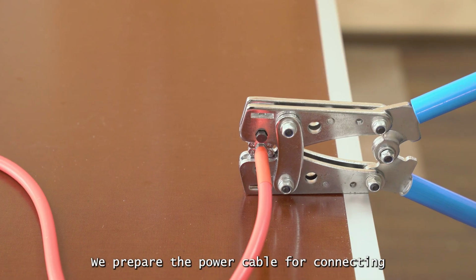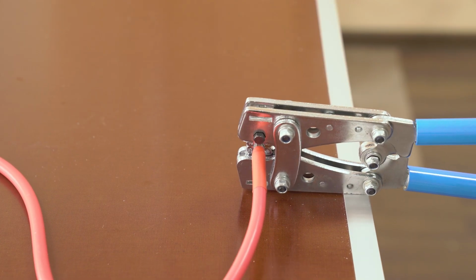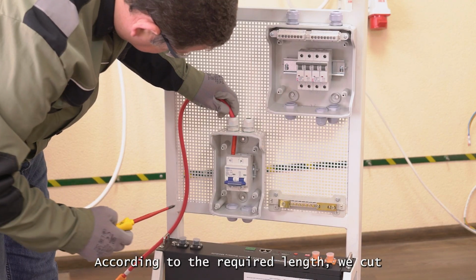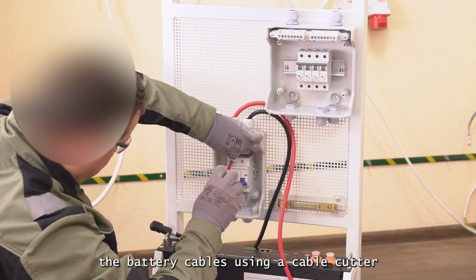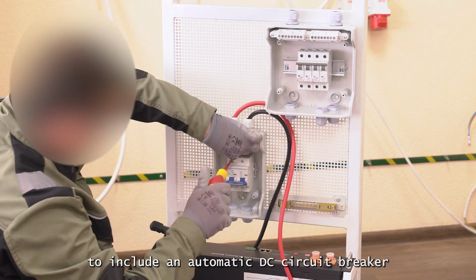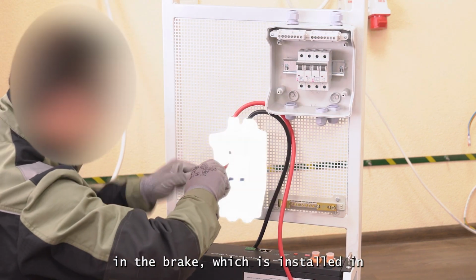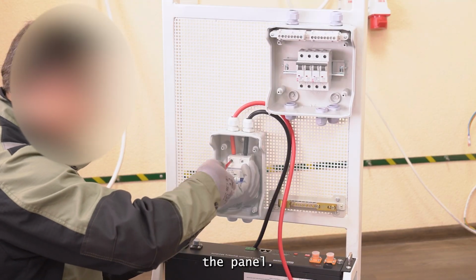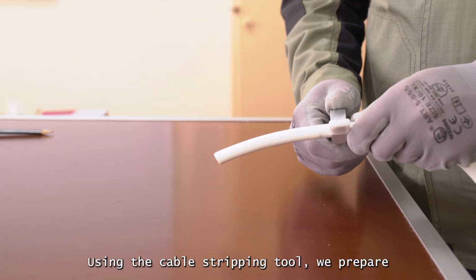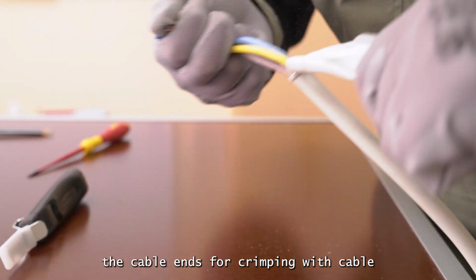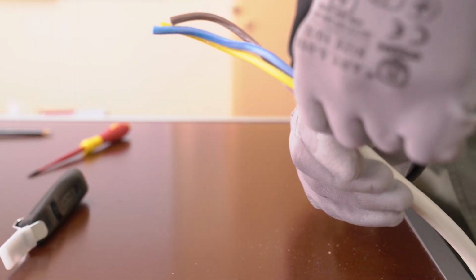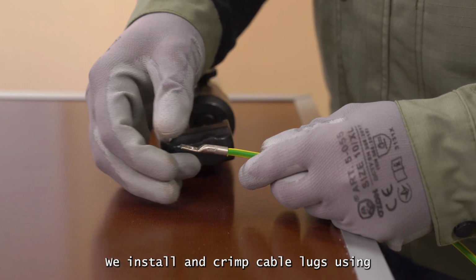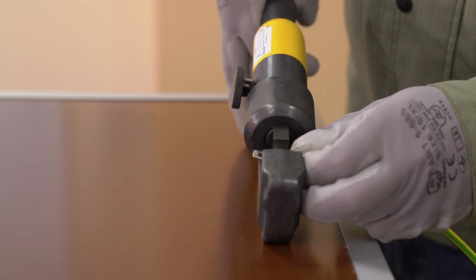We prepare the power cable for connecting the battery storage. According to the required length, we cut the battery cables using a cable cutter to include an automatic DC circuit breaker in the break, which is installed in the panel. Using the cable stripping tool, we prepare the cable ends for crimping with cable lugs. We install and crimp cable lugs using the crimping tool.